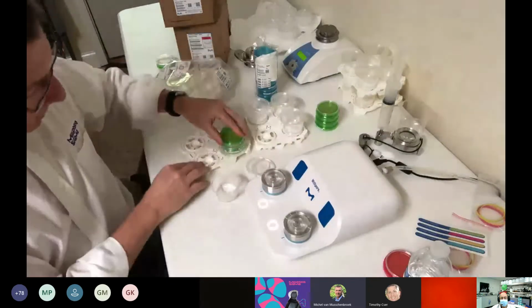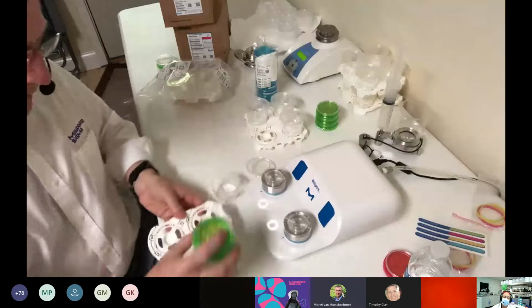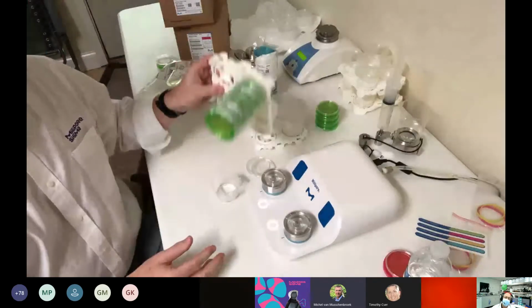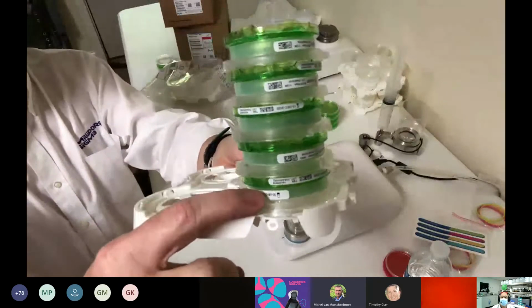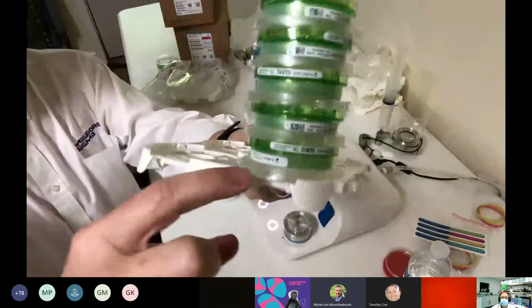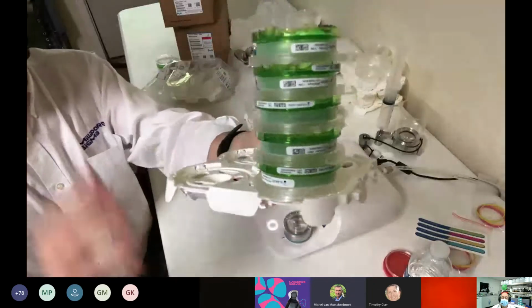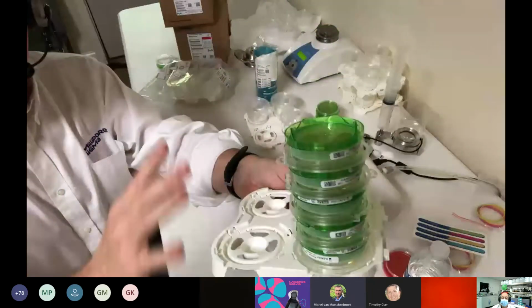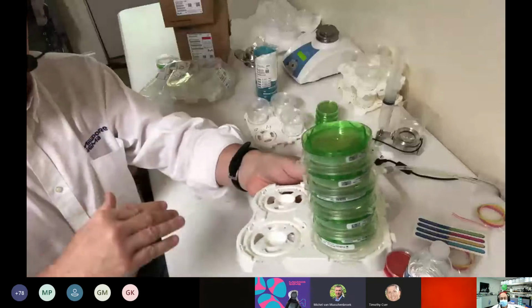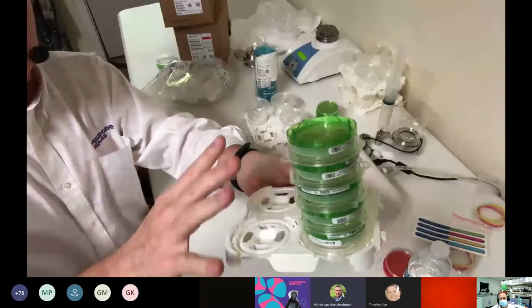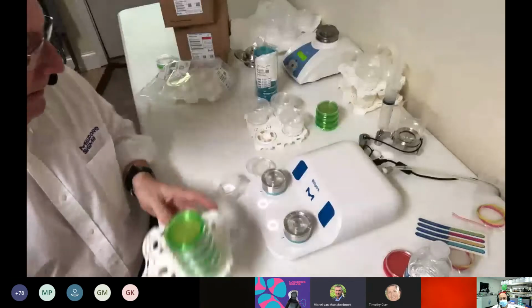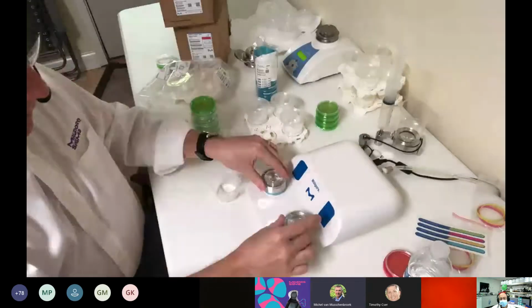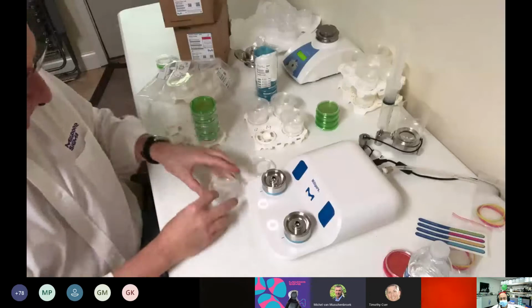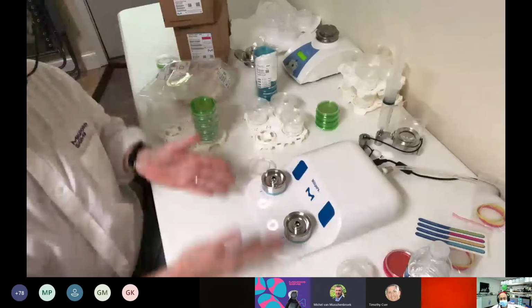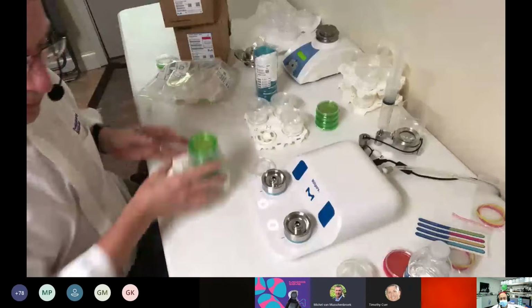And now I can actually stack these. I can stack them up to 6 high and not have a problem. And again, every single one of the media now has traceability, as well as the funnel that was used. So if there was any positive and you had to go back and do an investigation, you'd be able to find everything documented for you. Very, very nice system. At this point, it would just be a matter of removing the funnel supports and beginning the test again. So as you can see, it's really quite simple.